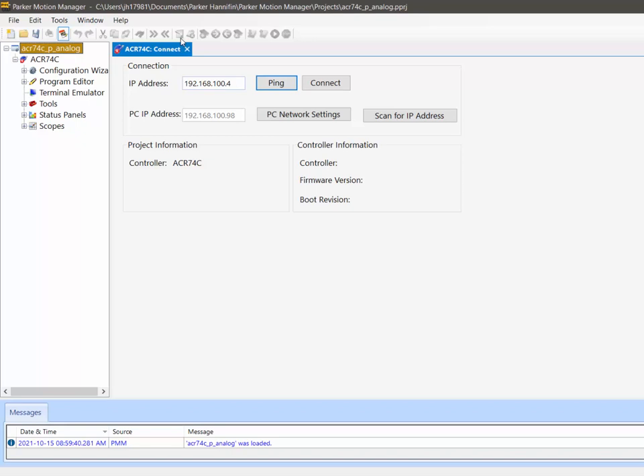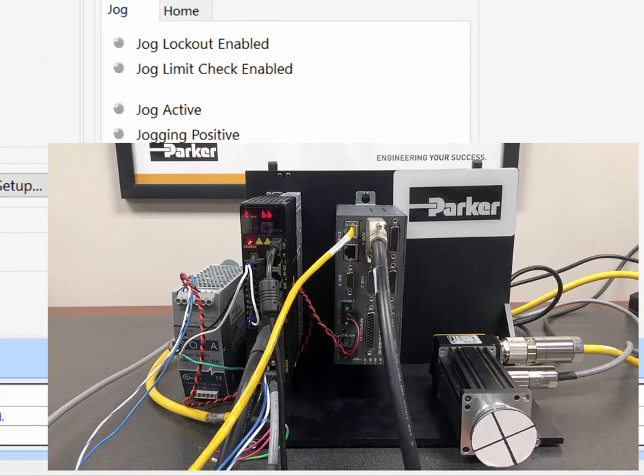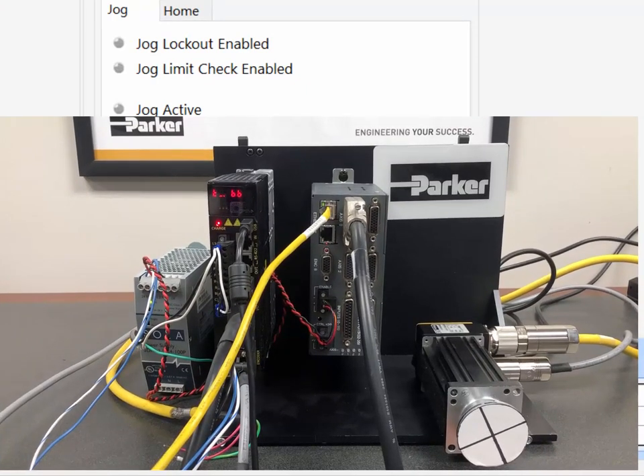In step and direction mode, the P-Series drive closes the position loop and you can do auto-tuning in the drive support tool software. In torque mode, the velocity and position loops are closed at the controller, so all tuning is done at the controller. To connect to the controller, you'll need the cable connected.